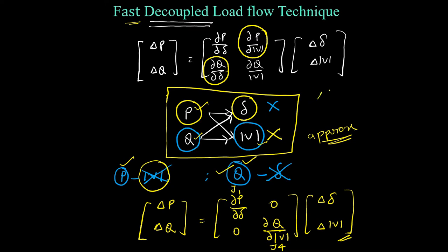That is why the NR method is a bit more complicated but accurate, because we are not taking any approximations there. But in the Fast Decoupled method, as compared to NR, the converging process will be very fast, the computation time will reduce, and memory will also reduce. However, the Fast Decoupled method is less accurate compared to NR. To improve accuracy, we have to increase the number of iterations.